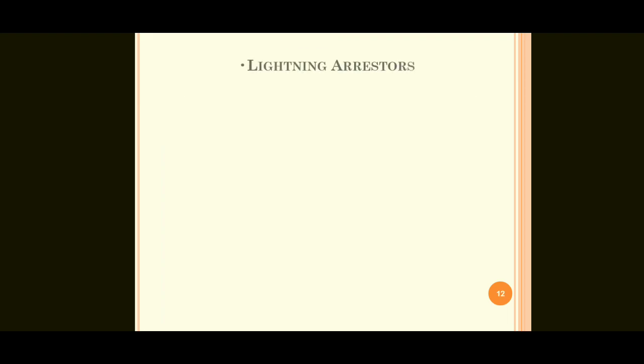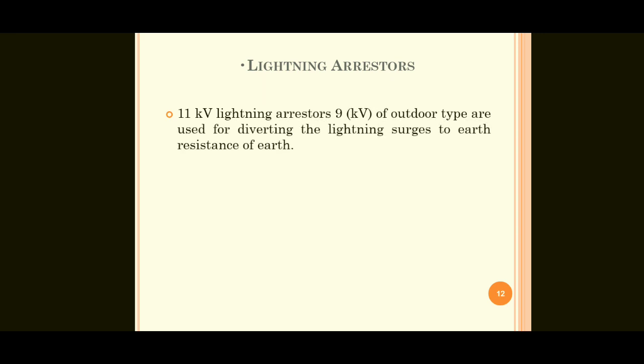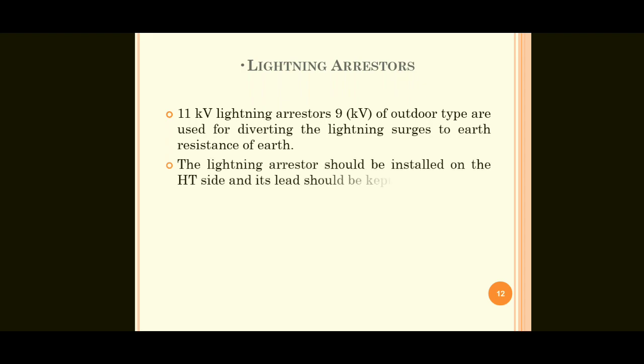Next one, lightning arresters. So here 11 kV lightning arresters of outdoor type are used for diverting the lightning surges to earth. We know very well the function of a lightning arrester, that is, protection from high voltage surges. These lightning arresters are placed on the towers, poles or substations or on the top roof of the house also, because simply it arrests or diverts the lightning surges to earth.